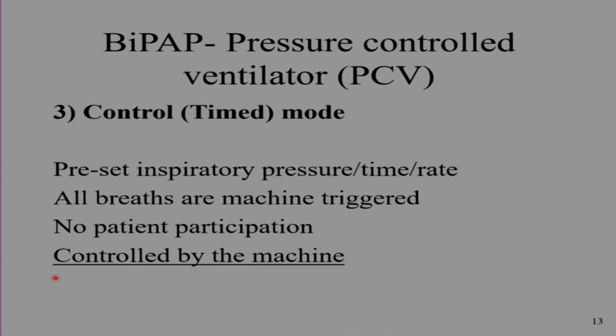The last one has nothing from the patient side - the patient does not do anything. It's fully controlled by the machine, with a preset inspiratory pressure and full support. All breaths are machine-triggered with no participation by the patient. There can be difficulty in synchronizing sometimes, with the patient fighting the machine.